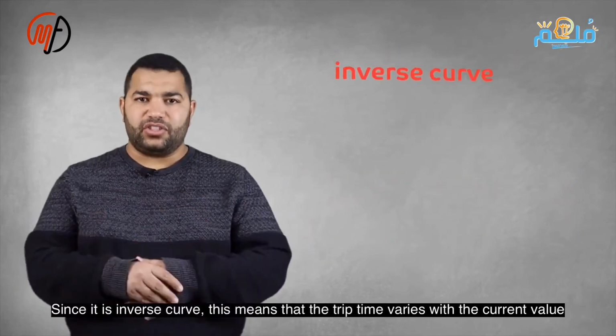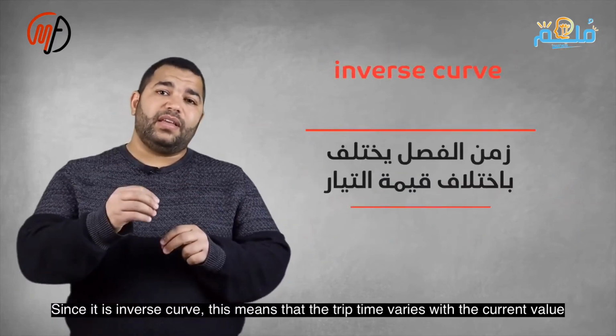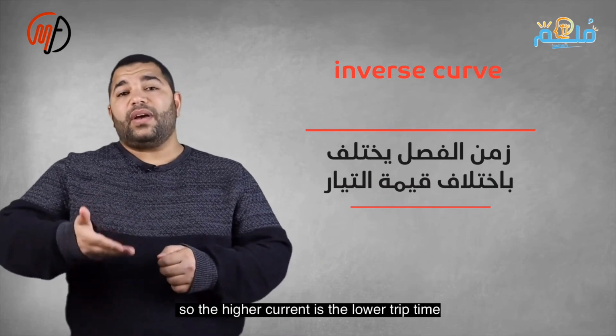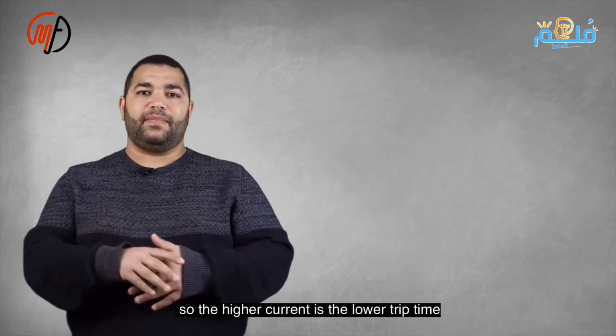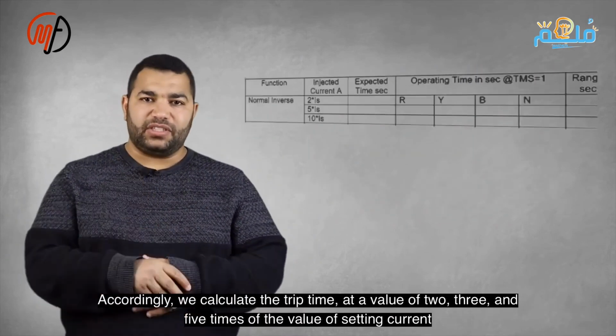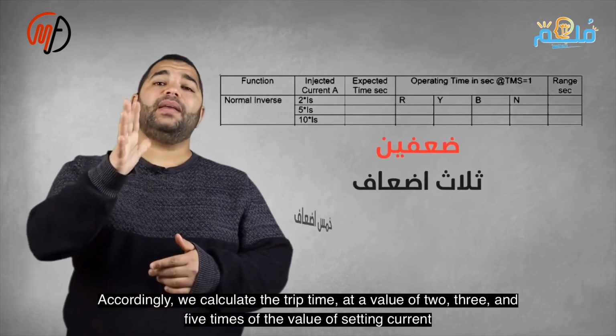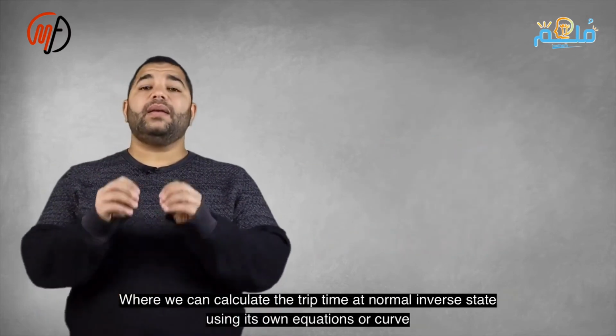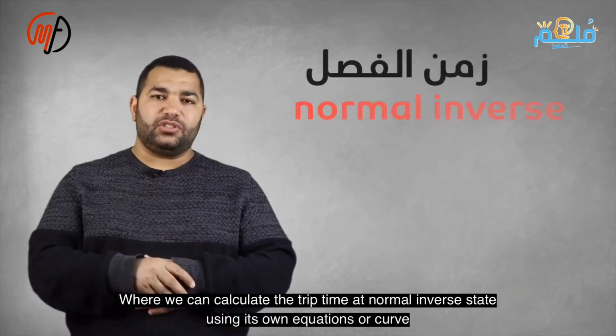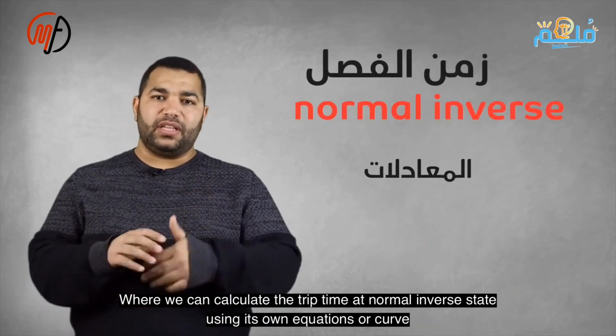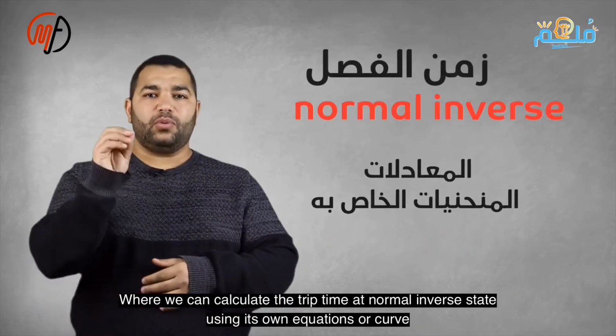Since it's an inverse curve, the trip time varies with the current value. The higher the fault current, the shorter the trip time. Therefore, we calculate the trip time at 2, 3, and 5 times the setting current value. We can calculate the trip time for the normal inverse either using the specific equation for the normal inverse or through the curves for the normal inverse.